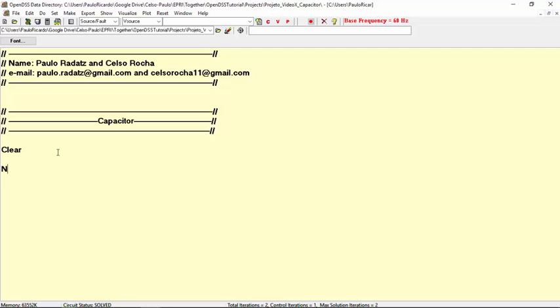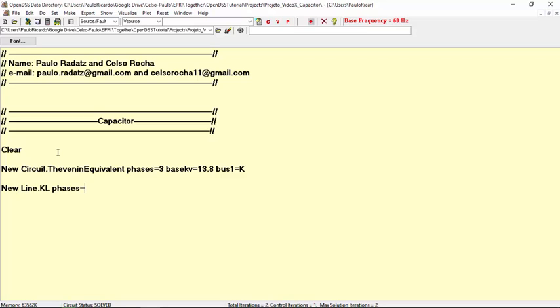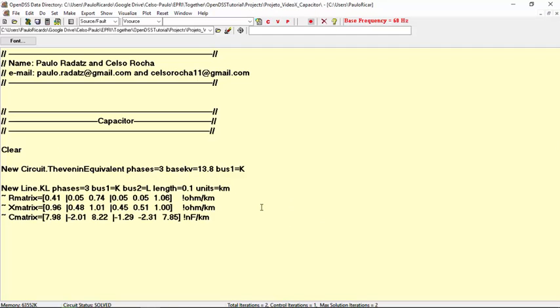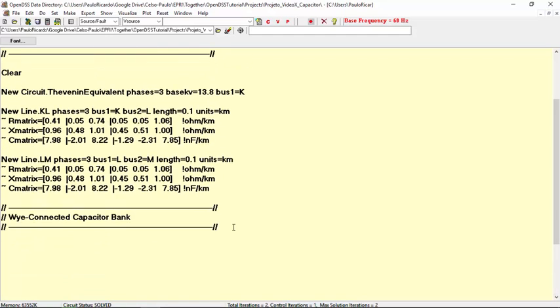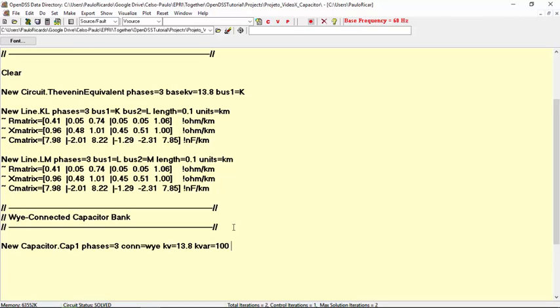In OpenDSS, firstly, I will create an element circuit. The first line defined will be the three-phase line, named as KL, connected between buses K and L. And the second one is the line LM, connected between buses L and M. Our capacitor bank will be named as CAP1. It has three phases, it's Y-connected, its rated voltage will be 13.8 kV, rated power of 100 kVAR, and it's connected to bus L. Let's solve the circuit and check the powers in the elements report.